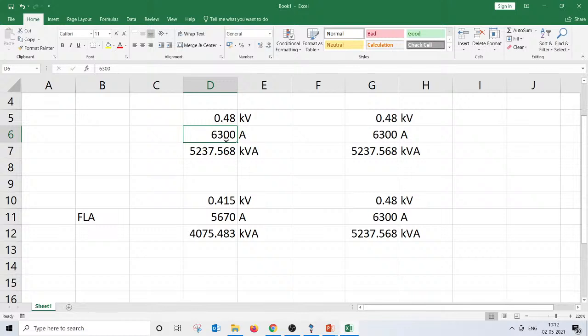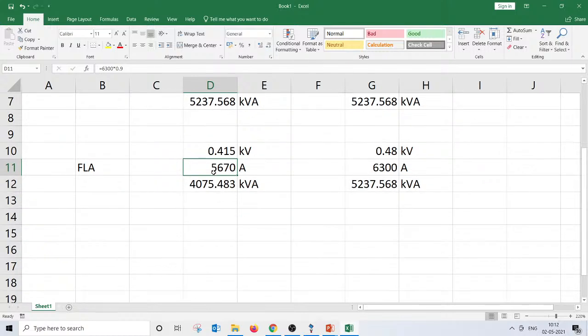That means you can allow up to 6300 amps, but when there is a reduction in voltage, the current will increase. So you are taking a 10% margin at least. People may go with 20%, but at least a 10% margin is needed. So you can have a maximum of only a 4 MVA transformer, not really beyond it.